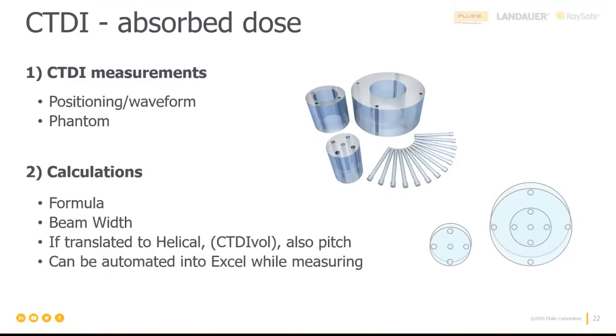So this was an example from free in air measurement. Let us now have a look at CTDI. So CTDI stands for CT dose index, and it is absorbed dose to the phantom. So it consists of two things, measurements and calculations. The measurements have to be done with a phantom and consist of a number of different positions in the phantom. The calculations on the other side have a formula. And to complete the calculation, we need to put in settings from the X-ray machine, like beam width and mainly beam width. And that's why we explained beam width earlier.